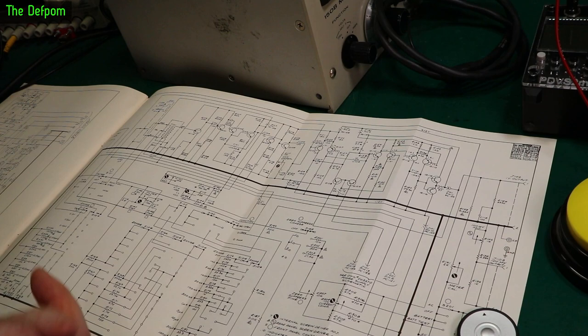Continuing on with this repair of the Keithley 150B. In the last section, I was trying to figure out if it even worked and it didn't. We've put an input voltage in, nothing showing up on the meter. It did seem to have power, the power supply rails look fine. The rails look okay, voltage looked okay.